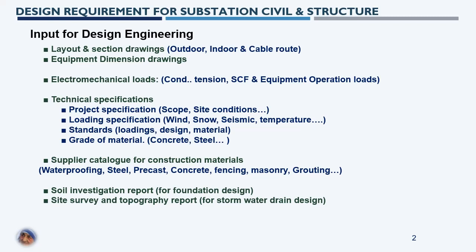The outdoor layout and sections provide detailed information about what structures and equipment are required for the substation system. They also provide various civil and structural engineering activity requirements, dimensions of various structures, how tall the gantry tower should be, the fixing height of line conductors, bay distance, types of equipment, access to equipment, control room building location, and other parameters required for civil and structural engineering design.